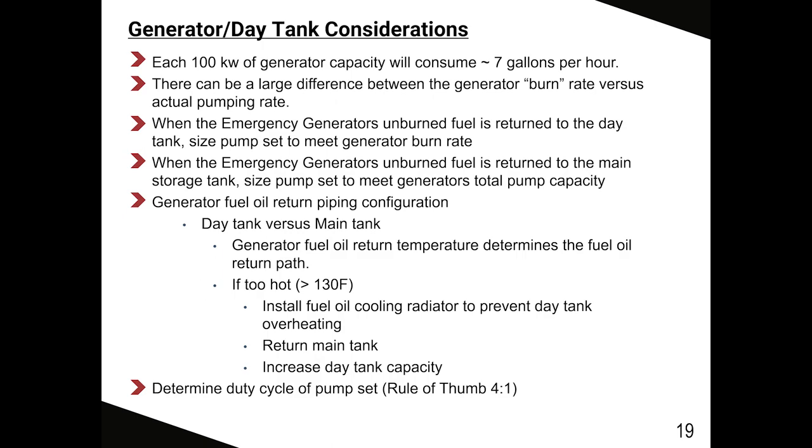Then you determine the duty cycle of the pump set. Typically, on taller buildings, the rule of thumb is 4 to 1, and this could be for buildings 30 stories up. Sometimes with 3 or 4 or 10 story buildings, you may only use a duty factor of 3 to 1.